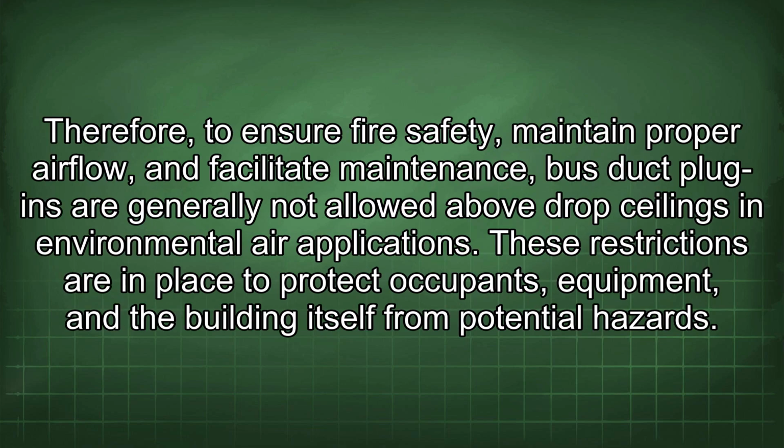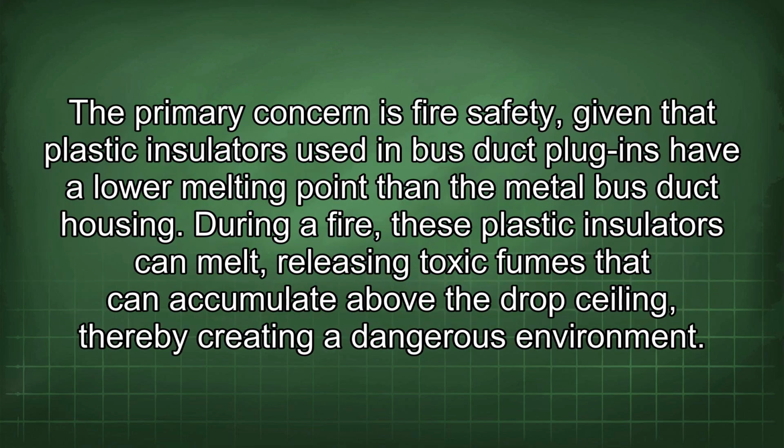Therefore, to ensure fire safety, maintain proper airflow, and facilitate maintenance, bus duct plug-ins are generally not allowed above drop ceilings in environmental air applications. These restrictions are in place to protect occupants, equipment, and the building itself from potential hazards. The primary concern is fire safety, given that plastic insulators used in bus duct plug-ins have a lower melting point than the metal bus duct housing.